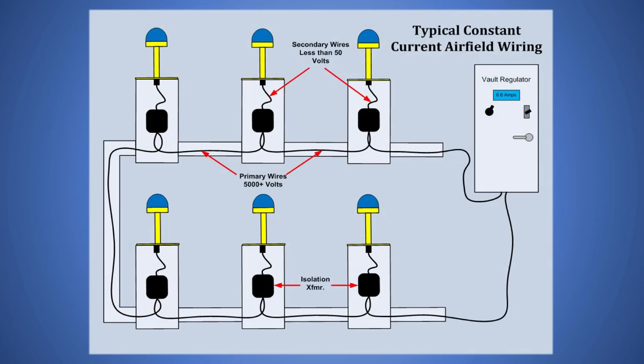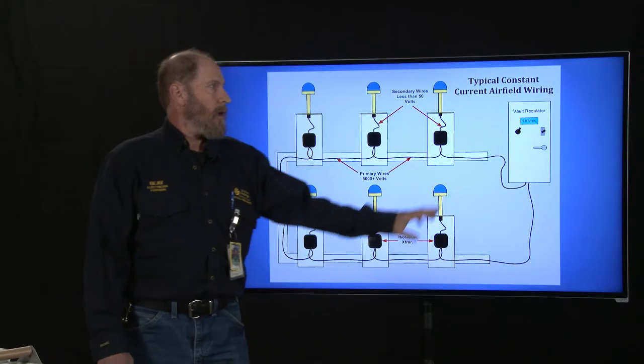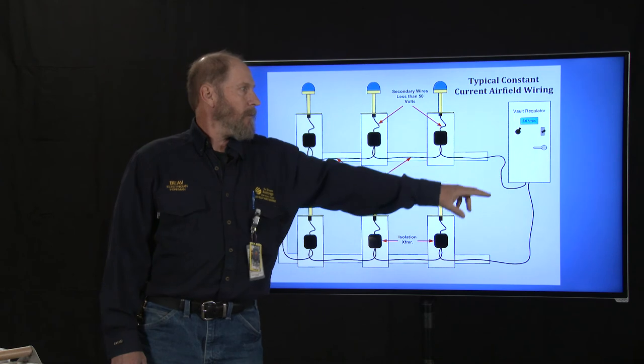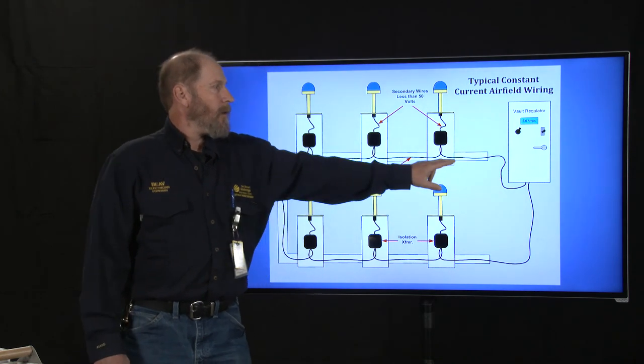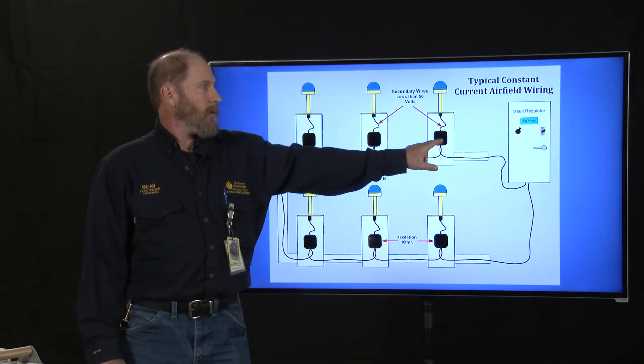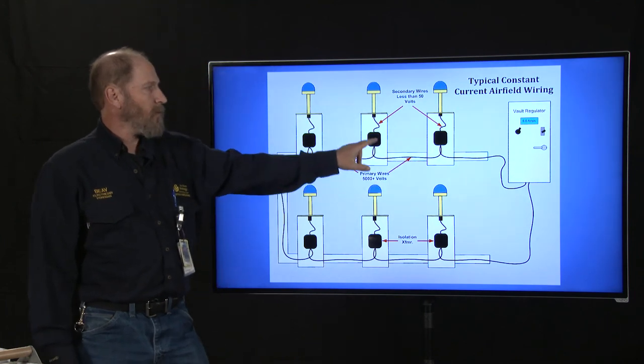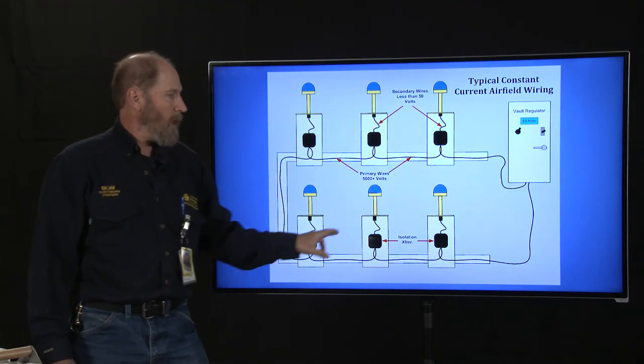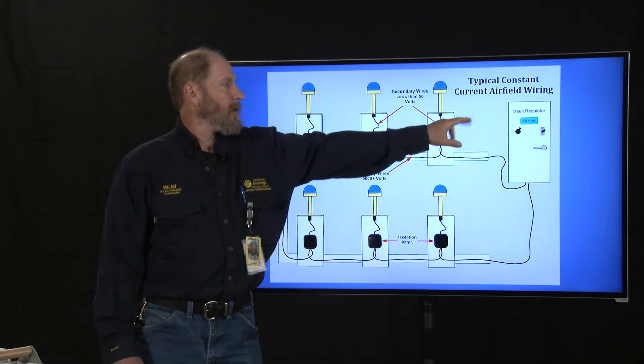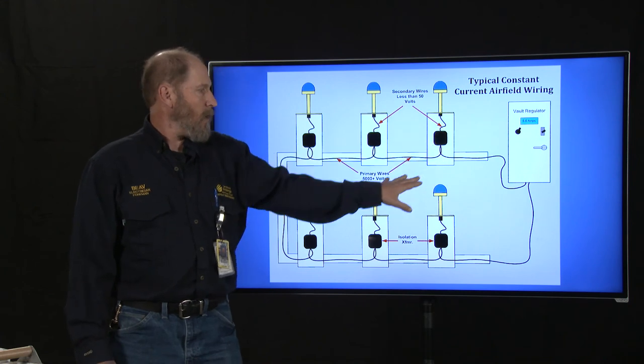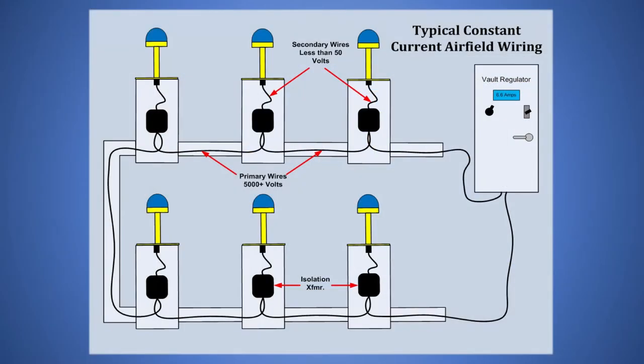So a constant current system is extremely simple. It's a series loop. You have your constant current regulator. The wires come out, go through a transformer. It goes on to the next one and on through the transformers and forms a loop back to the regulator. And these wires coming from the regulator can be up to 5,000 volts. We call this our primary wiring.